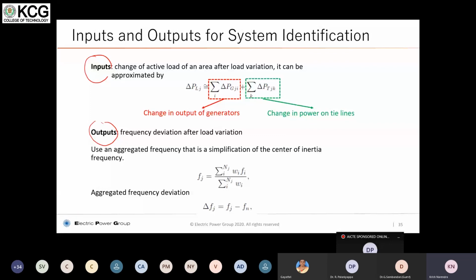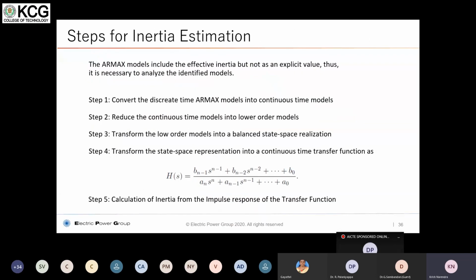Now, how do we do that? As I told you, the measured frequency can come from different places depending on the position of the PMU. But you can still evaluate the center of frequency using the technique shown here by giving proper weightages. In our case, we gave a weightage of 1 to all of them. The aggregated frequency is calculated as the frequency of what you calculated on the system frequency, Fn. When the delta Fj is found, it is then used in the 4-step methodology here.